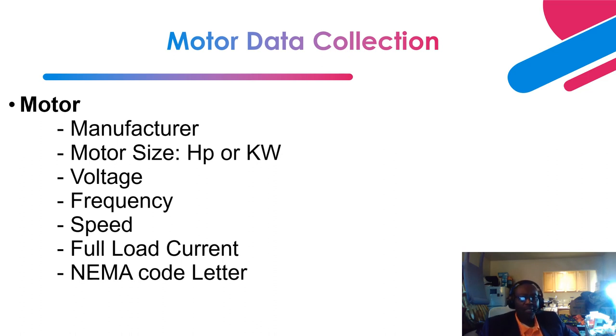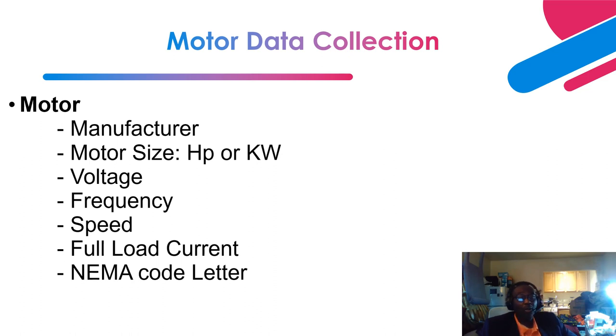For motors, in most industrial facilities there are many large motors. For Arc Flash studies, motors greater than 50 horsepower are important to model; motors below 50 horsepower can generally be ignored. For motors greater than 50 horsepower, you need the manufacturer, motor size (horsepower or kilowatts), voltage, frequency, speed, full load current, and the NEMA code letter. The NEMA code letter provides input to the locked rotor current. NEMA code letters include A, B, C, D, and E.